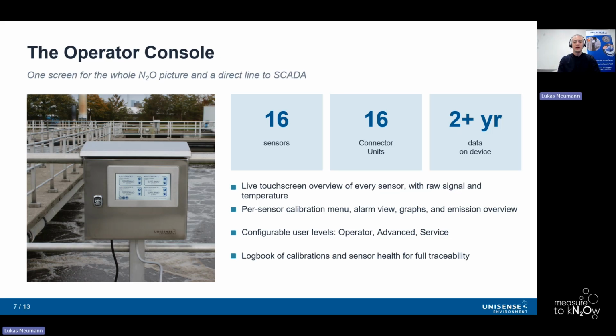As before, we have multiple user levels, so you can lock down the system for plant staff versus service techs and pick what they see and what they have access to. And then, of course, we have full traceability, where every calibration is logged. It's important to mention here that the console runs whether or not it's connected to the SCADA, so your data is never lost. It's logged internally first and then pushed out to the SCADA.